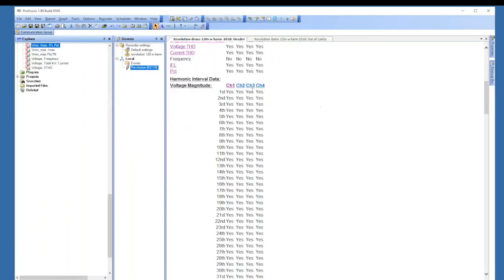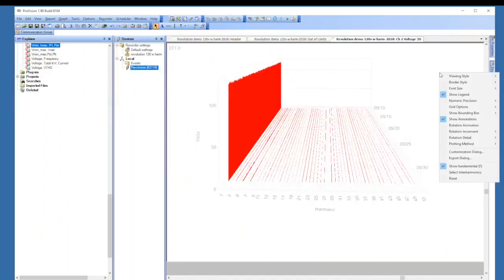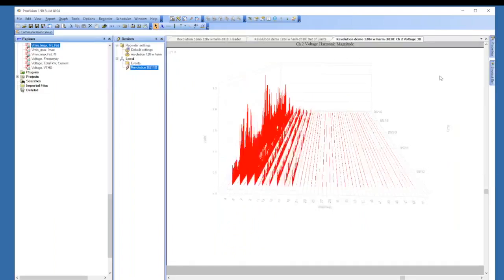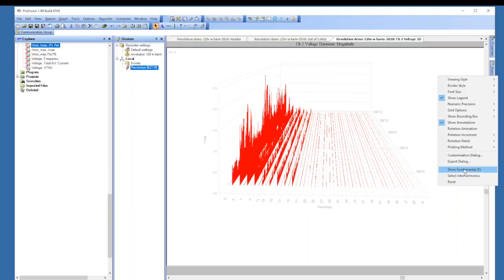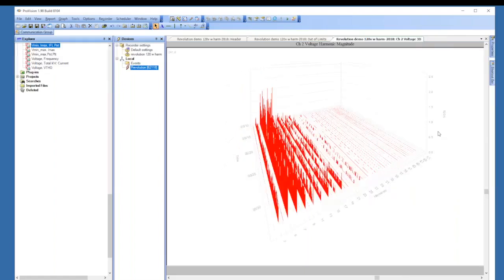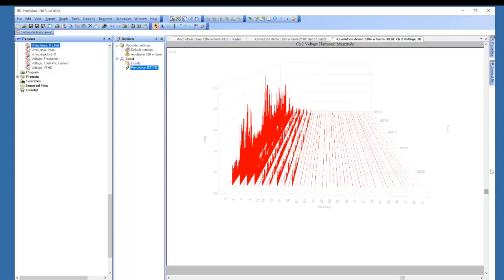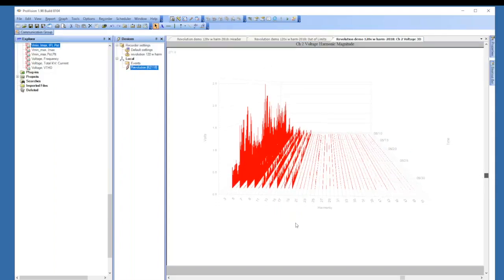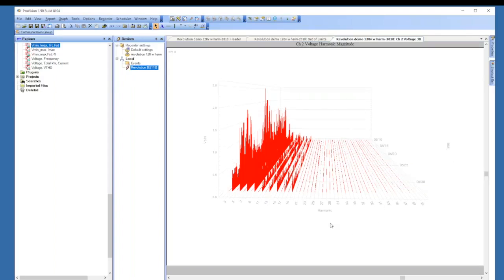Now, we did also record harmonics. If we click on harmonic in the header report, we get what I call the waterfall graph. We take the fundamental off. Did it pretty quick. So you right-click, and there's a show fundamental. You take that off, and you get an idea of where your harmonics are. And you can see, and it's pretty much typical too. Usually the harmonics fall fairly early, in the low numbers, and as you get towards the higher numbers, they fall off. You will see some in the 27s sometimes if there's some issues going on with motors and things like that.